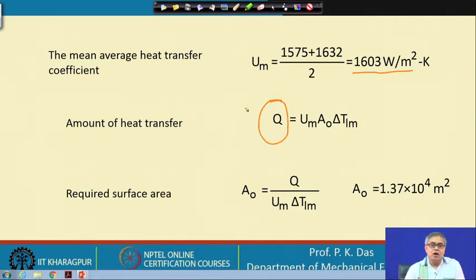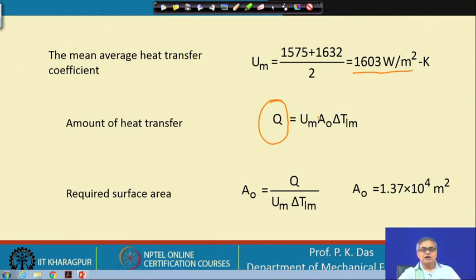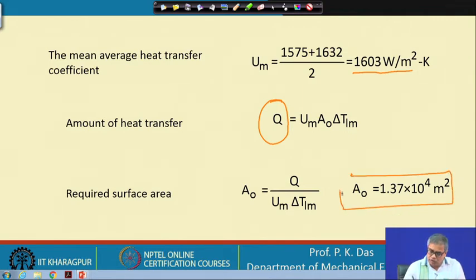Now we know Q, we know the average heat transfer coefficient, and we know the log mean temperature difference. The only unknown is A_o — the outside tube area — since the average heat transfer coefficient was calculated based on the outside area of the tubes. From Q = U_avg × A_o × LMTD, we can calculate A_o.